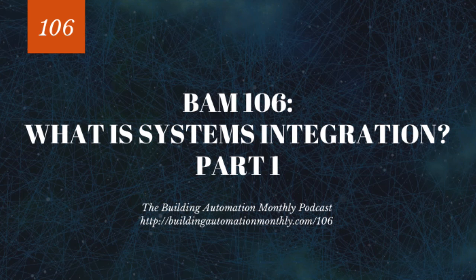So that's another example. And the third and final one is going and working with electrical information. So you may be able to get an electrical feed from your local utility. And what I would often like to do is pull that electrical feed in, as well as the electrical runtime equipment data, and basically create a BTU chart, really realize how many BTUs I'm using, as well as get a full snapshot of the entire utility consumption and demand of the building. That way, if you want to do demand reduction, if you want to do some form of load reduction, you're able to do all that.